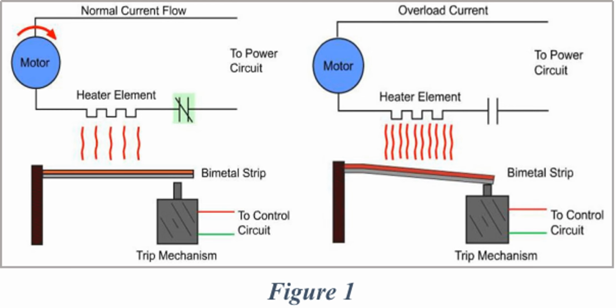There are two major types of overload relays: thermal overload relays and magnetic overload relays. In this article, we will take a look at the comparison of both relays in terms of their different aspects. Working principles. A thermal overload relay is an electronic element, which is generally used in phase failure shielding, overcurrent protection, and protection of AC motors, and other electrical devices and circuits from overheating. During the overload condition, this relay switches off the faulty circuit to protect overheated circuit as soon as the temperature rises above the threshold value.